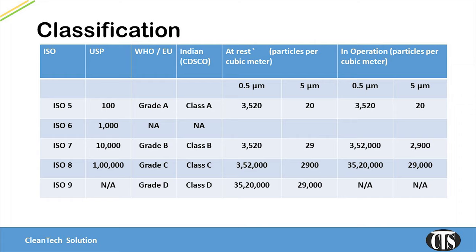In Grade C or Class C or Class 100,000, the particle size at rest condition is similar to Grade B's particle sizes in operation condition. In operation condition, the particle sizes in Grade C are 3,520,000 and 29,000 respectively for 0.5 micron and 5 micron. We will notice that similar particle sizes appear for Grade D at rest condition. In Grade D, we do not count the particle size in operation conditions.